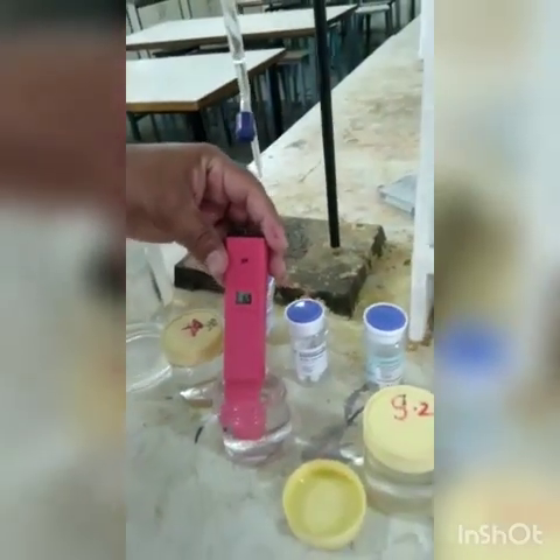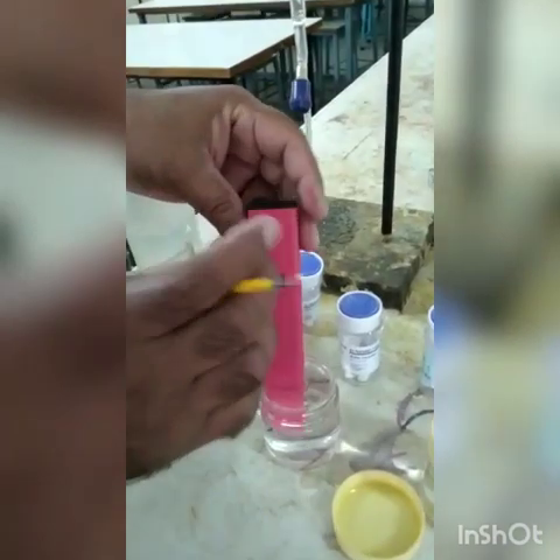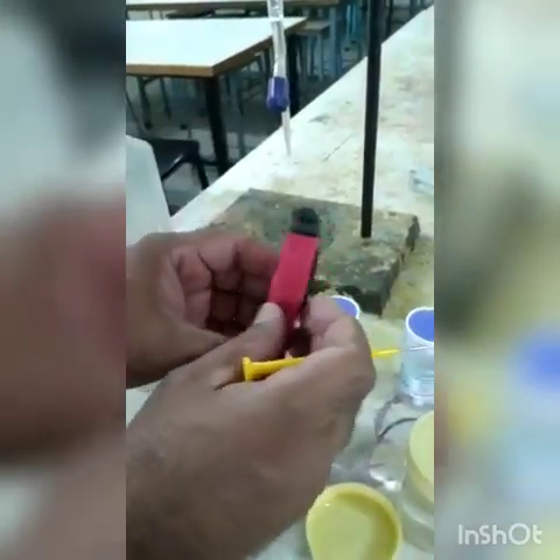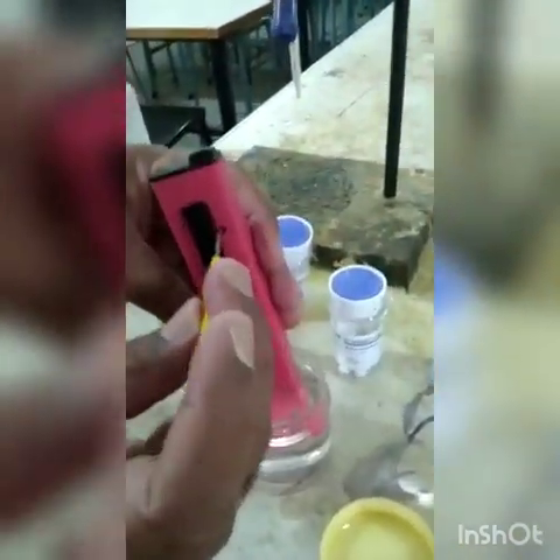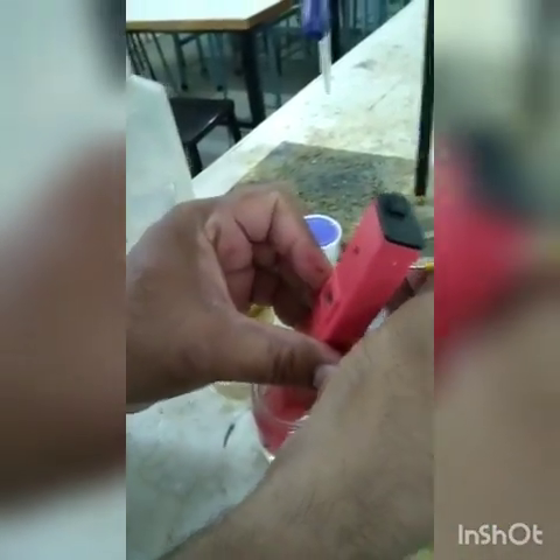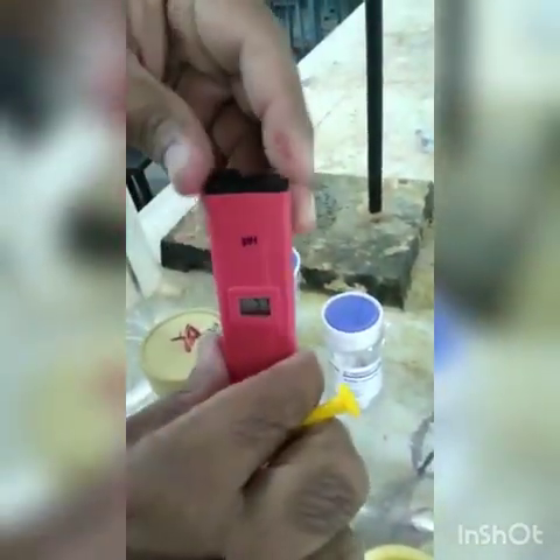So there is a slight deviation. So we will adjust this to pH 7 using a small screwdriver and a small screw which is there. So we have to adjust it for pH 7. As you can see, it is adjusted now to pH 7. Again wash it with distilled water.